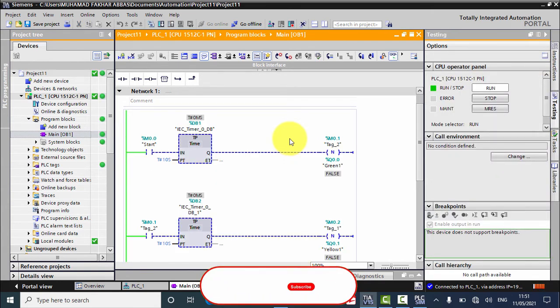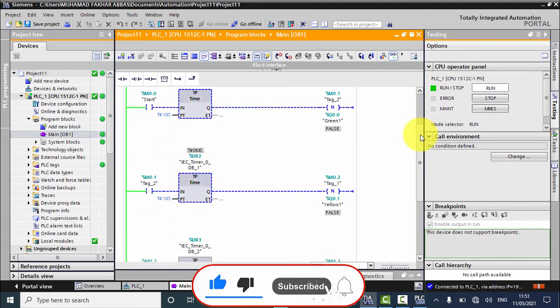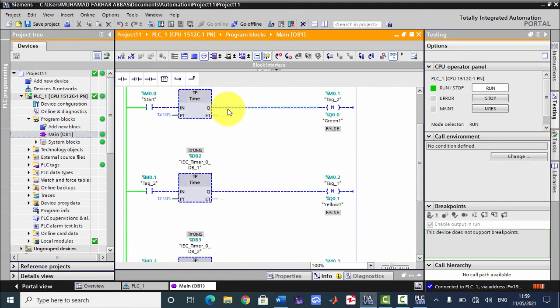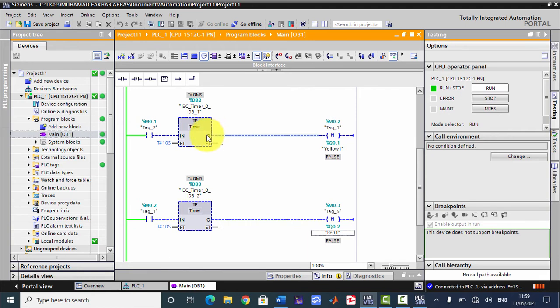Now I will explain why I used the negative edge output coil. When we press M0.0, our pulse timer turns on and keeps output Q0.0 on for 10 seconds. M0.1 will only turn on when the pulse timer changes state from 1 to 0 — that is, when Q0.0 goes to 0, M0.1 becomes 1, acting as a start button for the next timer. Similarly, when that timer changes from 1 to 0, the next negative edge is detected and starts the following timer, turning on its output.